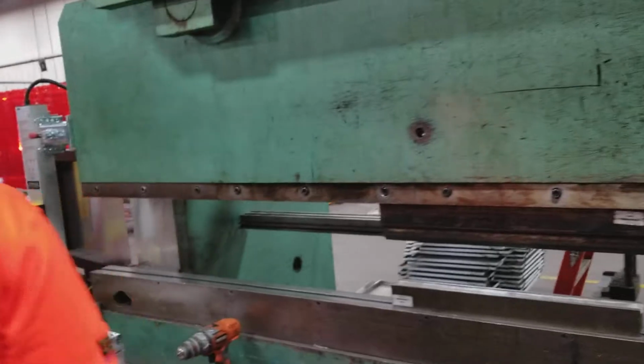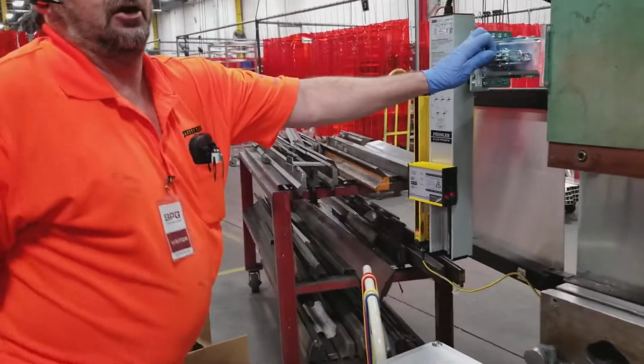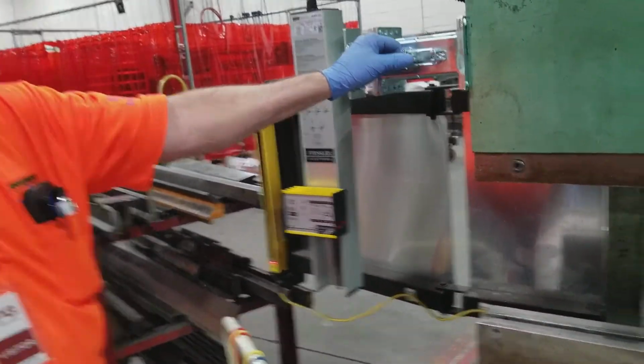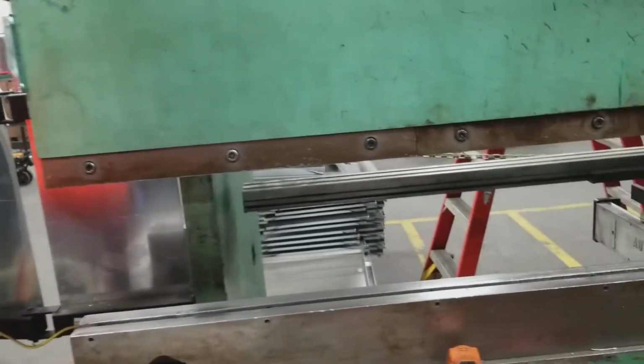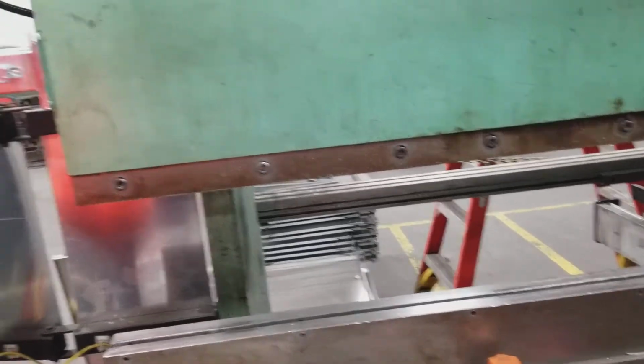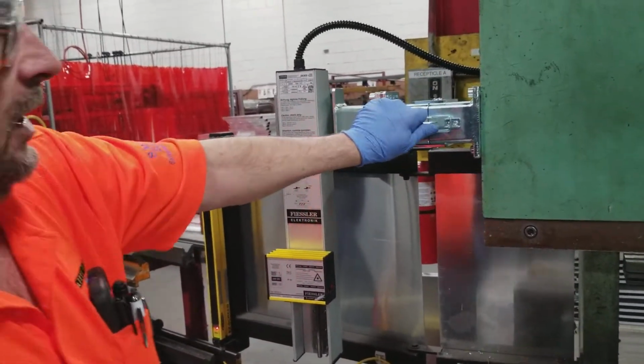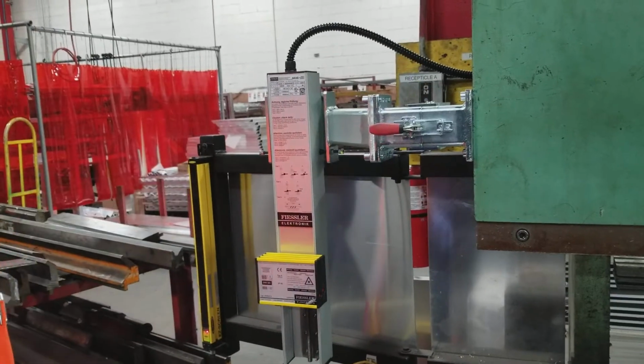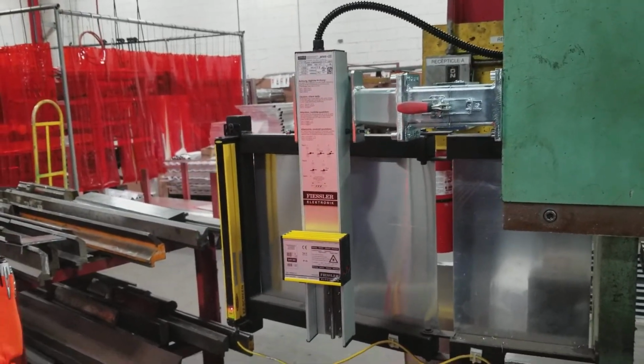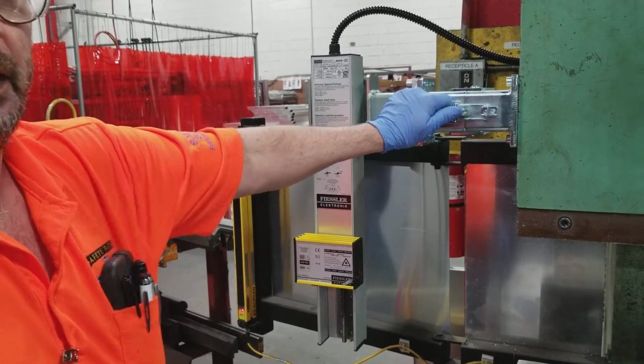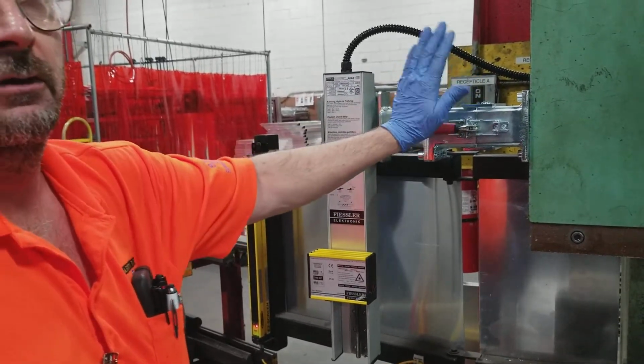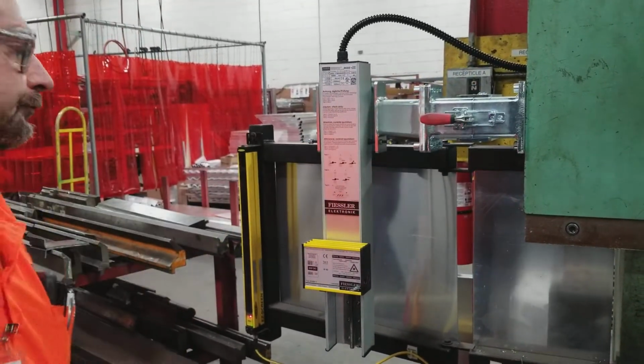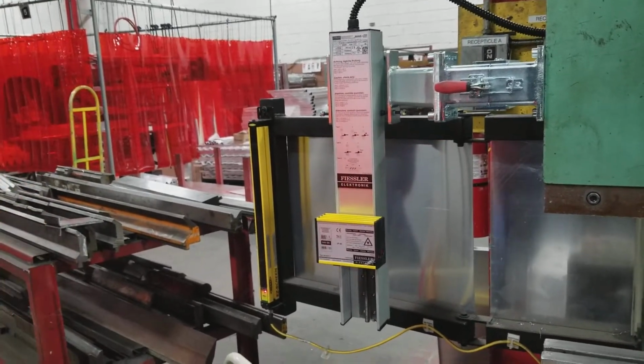If we do have an alignment issue, the first thing we always want to check is this handle right here. Because if I just pop it loose just a little bit, see how far it's gone out? Always make sure when you push this in, it snaps or pops. If you hear it or feel it snap or pop, you're good to go. It should lock it right in. Never do that closed fist because you will lose a fingernail. Always do it palm open.